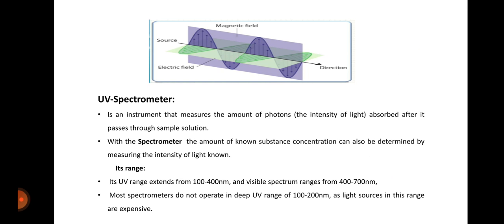UV spectrometer is an instrument that measures the amount of photons, the intensity of light absorbed after it passes through sample solution. With the spectrometer, the amount of known substance concentration can also be determined by measuring the intensity of light.